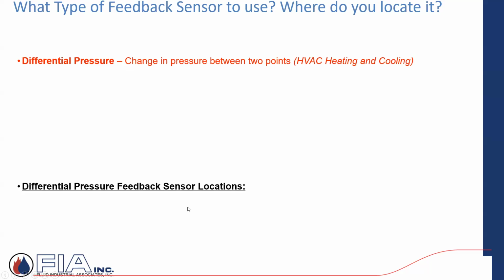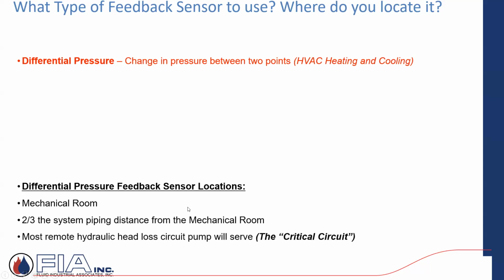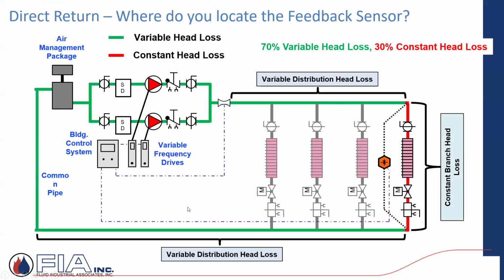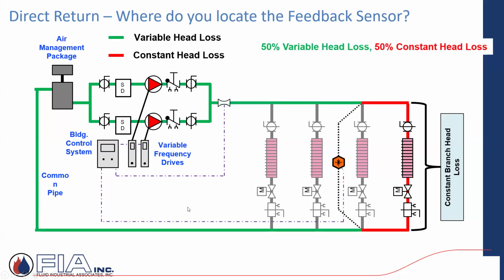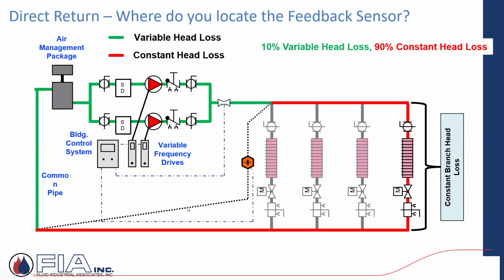Where do I locate it? Like we talked about, mechanical room, 2/3, or remote. Ideally, we want to get it out to that critical circuit, that far-reaching terminal unit. And again, just reiterating, what's the variable? What's the constant? If I can increase the amount of variable, that gives me the greatest amount of speed reduction, which is energy savings. So I have examples. Remote, if I go halfway through, 50-50, it's influencing the constant, so it's reducing my variable. If I go all the way back to the mechanical room, which sometimes happens, I've really reduced that variable and I have a built-in constant that I have to honor. So it's really important where those sensors are, that we want to get them remote as best we can.